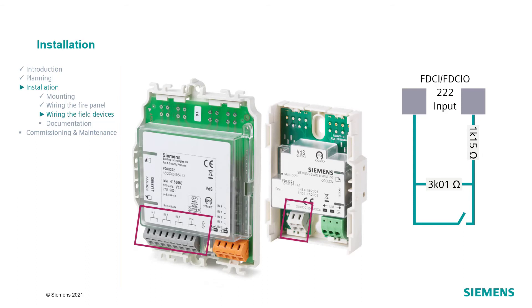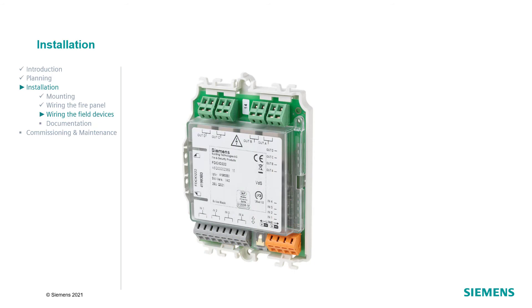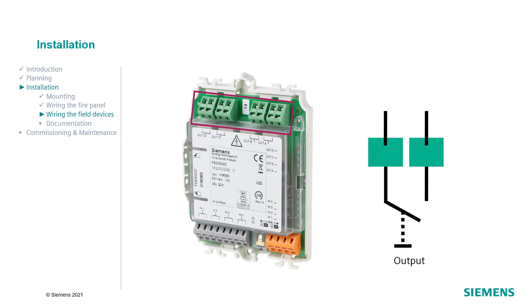When a short circuit or an open line occurs on one of the input lines, a fault message is transmitted to the control unit. The inputs must be potential free. The outputs of the I.O. module FDCIO222 can be used to activate control functions like closed door for example. The outputs are potential free relay contacts.